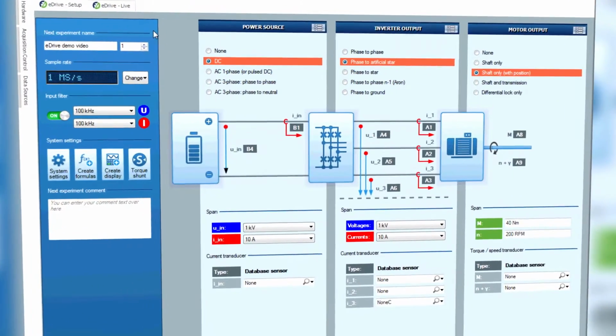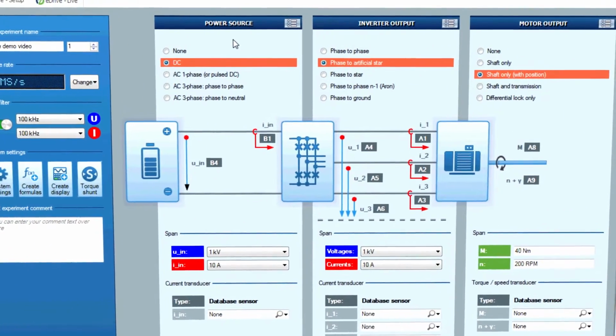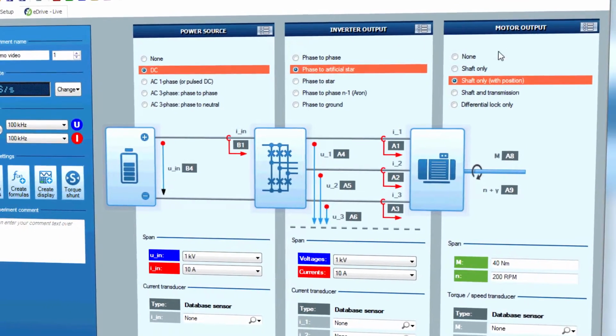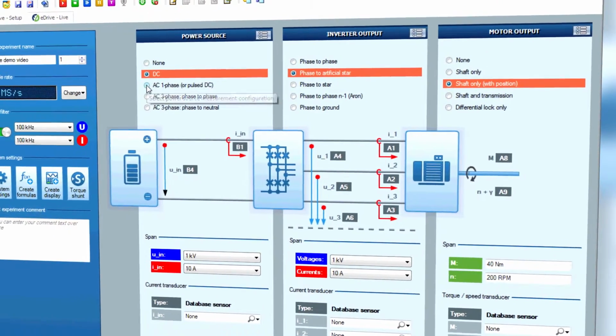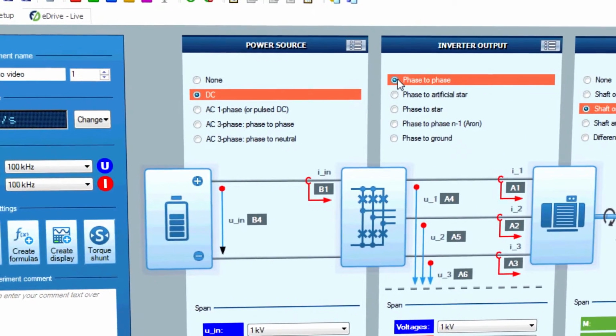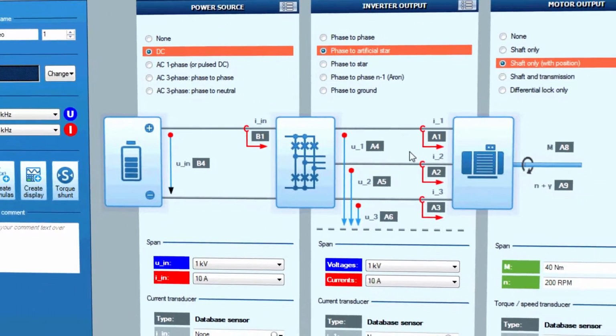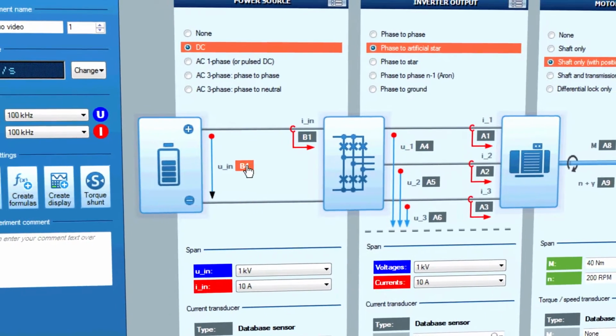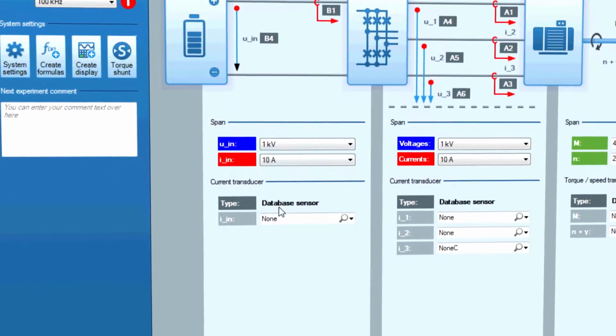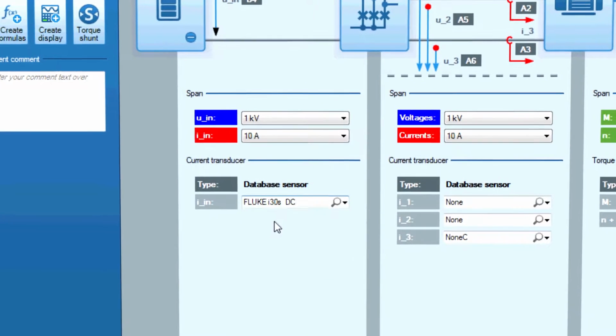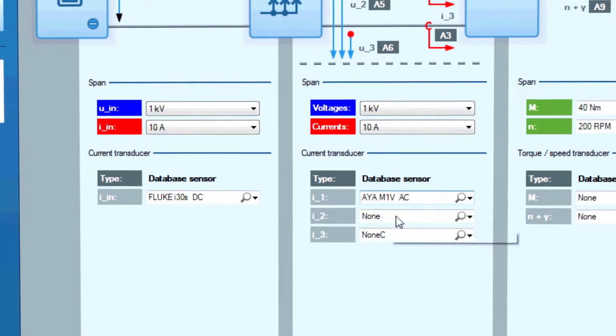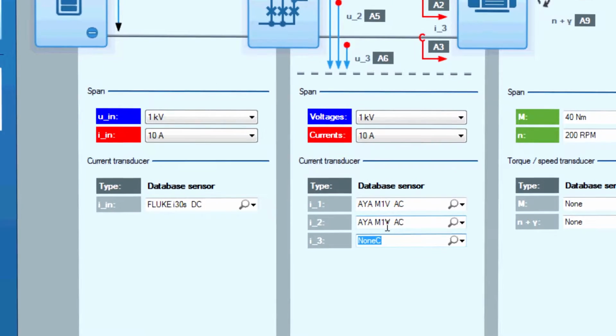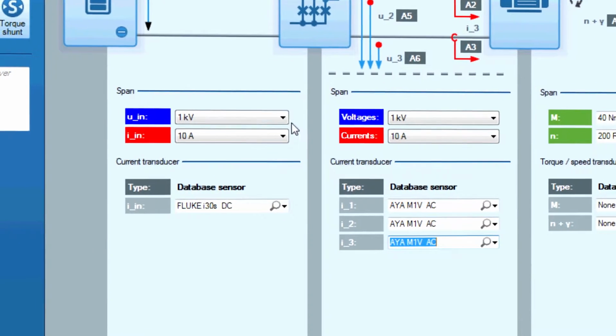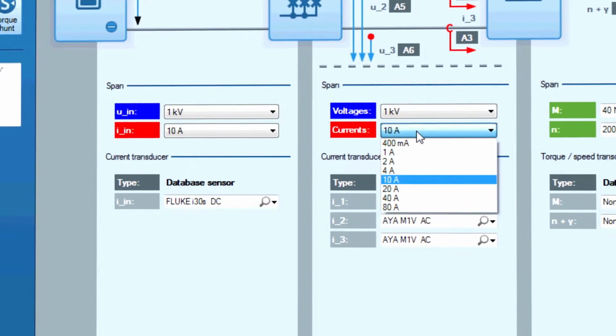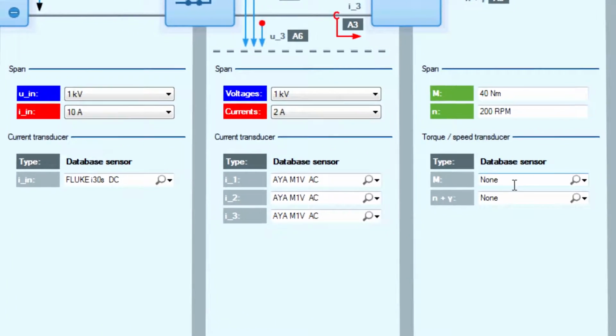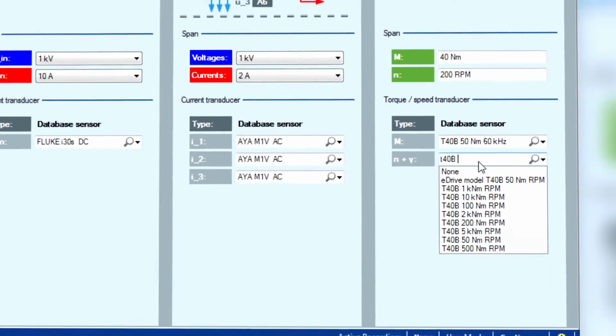The setup sheet of the software maps the application with a power source, an inverter, and an electrical machine. Different configurations can be selected, such as DC input or phase-to-phase measurement. The integrated wiring diagrams ensure error-free cabling. Select a sensor from the built-in sensor database to configure the input amplifier, including sensor calibration data used for scaling the sensor output into physical units. Then, select the expected signal ranges for voltage and current. Finally, select the torque and speed sensor. Now you are all set to measure.